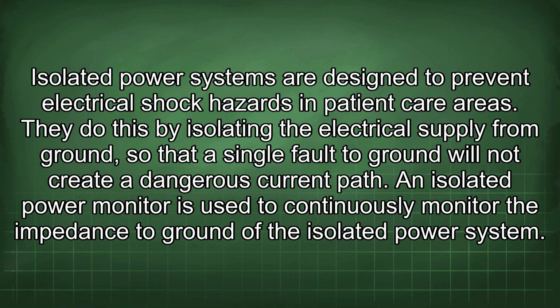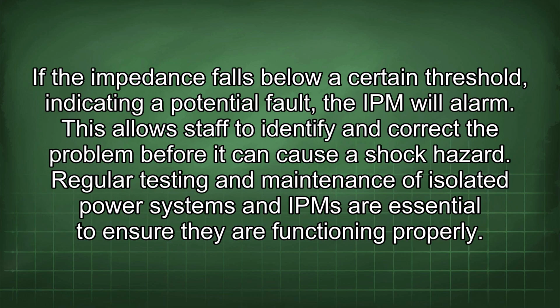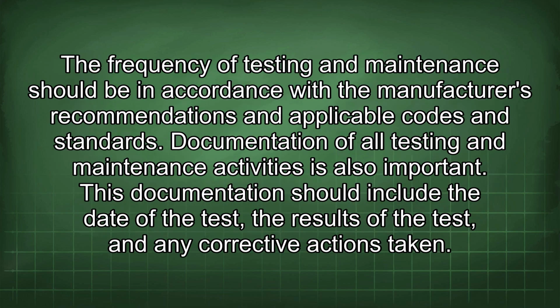a dangerous current path. An isolated power monitor is used to continuously monitor the impedance to ground of the isolated power system. If the impedance falls below a certain threshold, indicating a potential fault, the IPM will alarm. This allows staff to identify and correct the problem before it can cause a shock hazard. Regular testing and maintenance of isolated power systems and IPM are essential to ensure they are functioning properly. The frequency of testing and maintenance should be in accordance with the manufacturer's recommendations and applicable codes and standards.